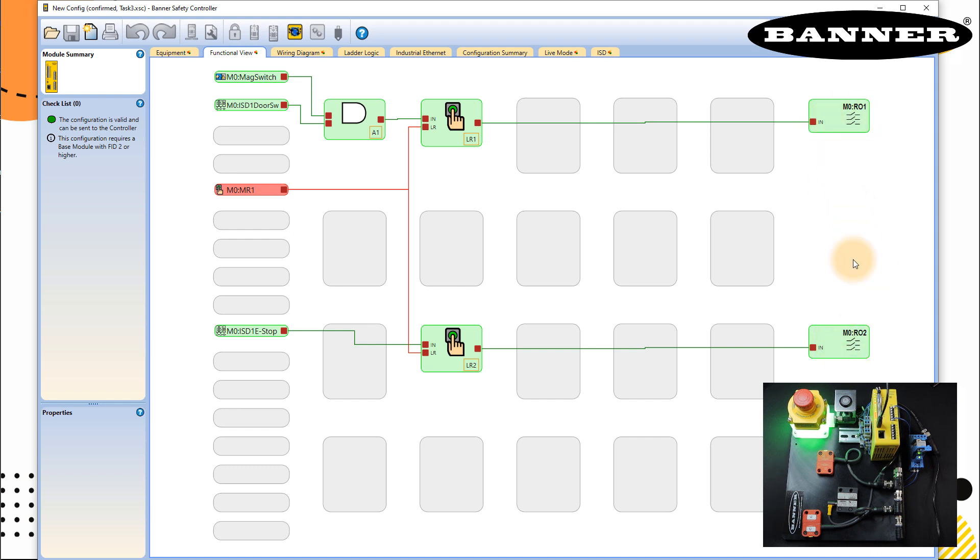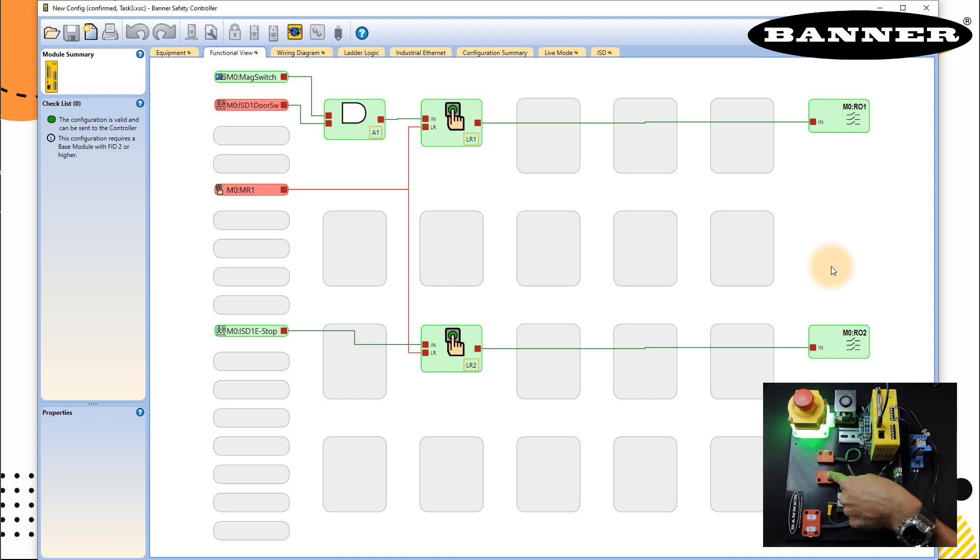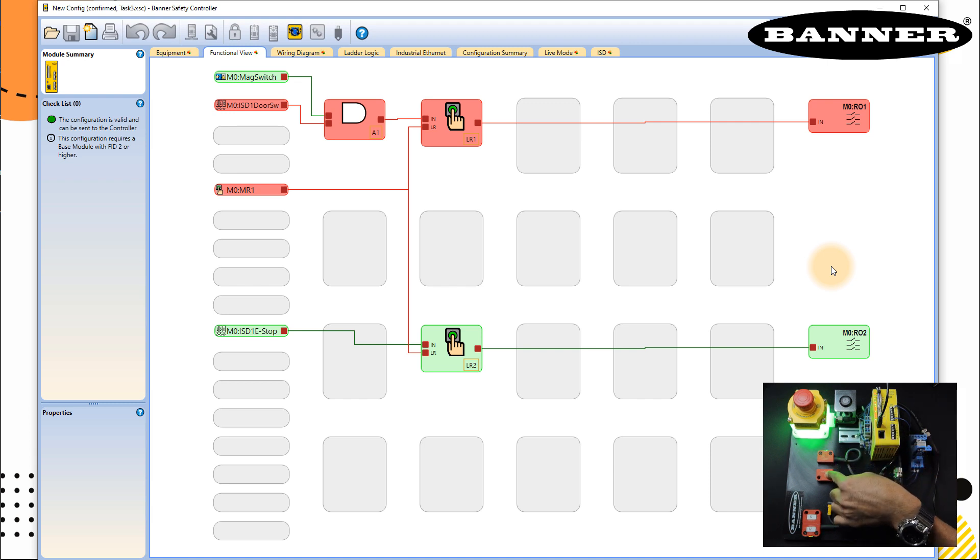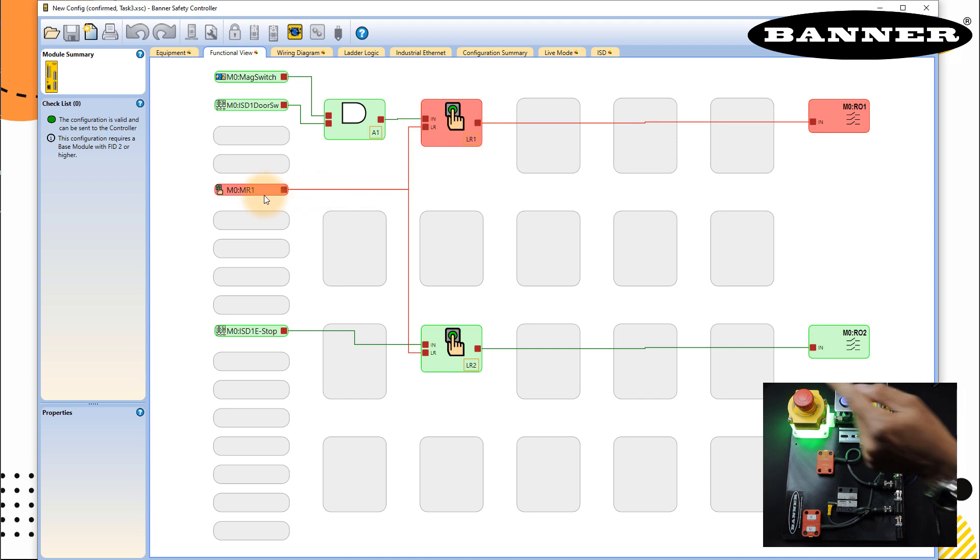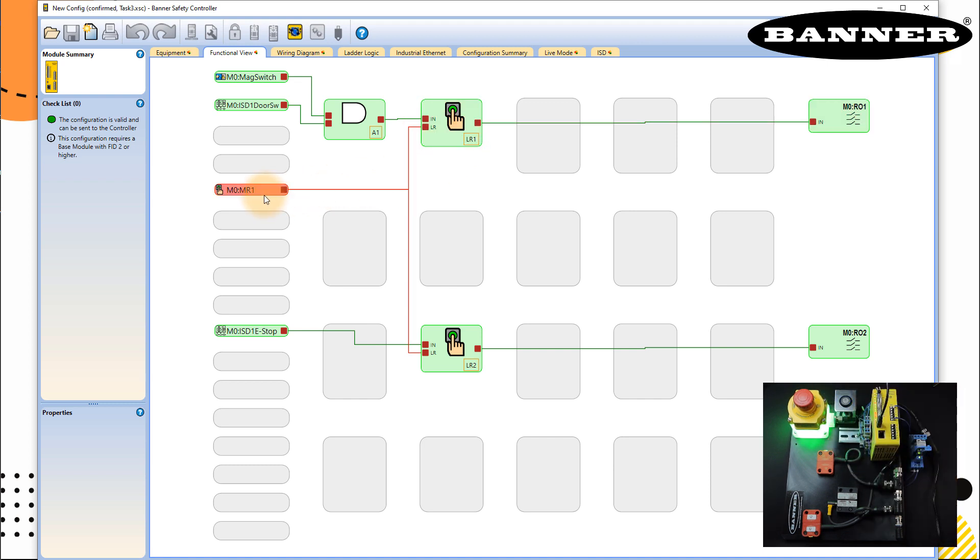Now these will get false if any of the safety circuits gives a signal. So let's try with this one. Output is off. Now if I bring back this sensor again, output will not get true unless we reset the circuit. This is the important part we have understood using LR block. So we have to reset the block again using an input. This will reset the output. So my output is true now.